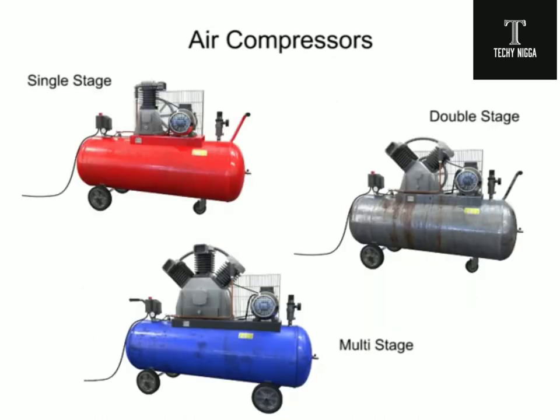If pressures of more than about 175 psi are needed, multi-stage compressors should be used. On these larger compressors, cooling may take place by circulating water instead of air.